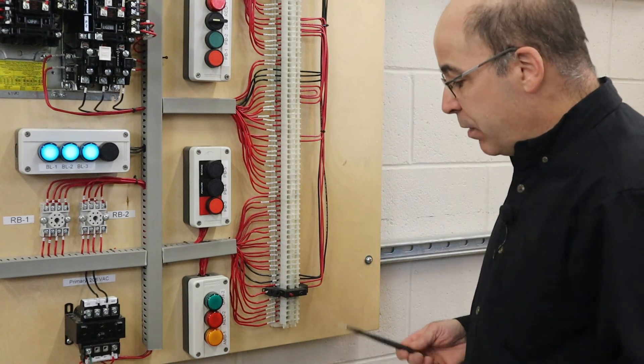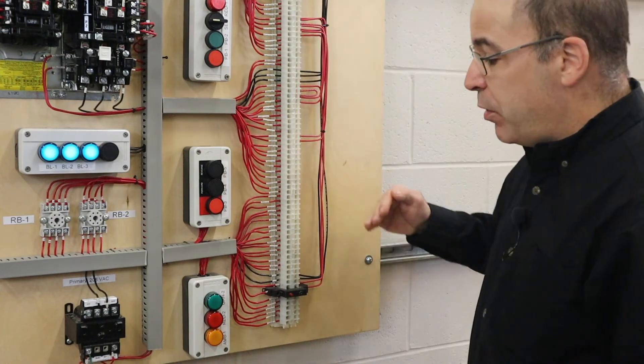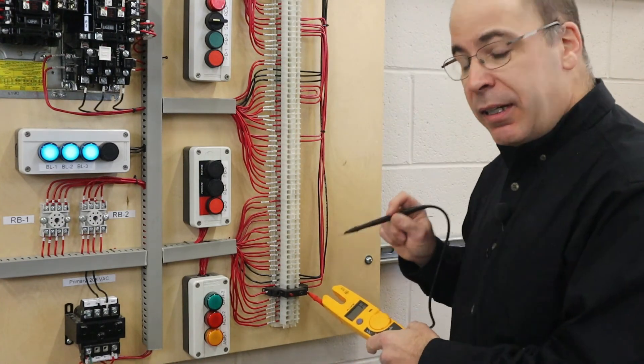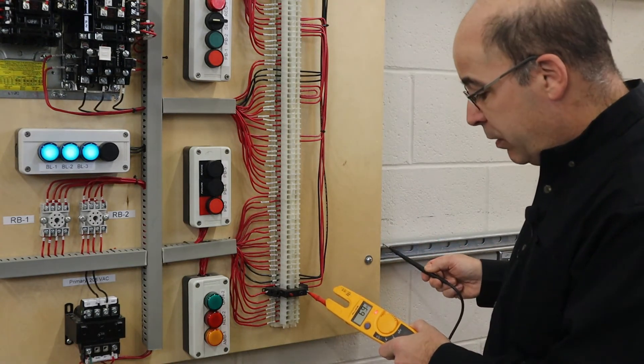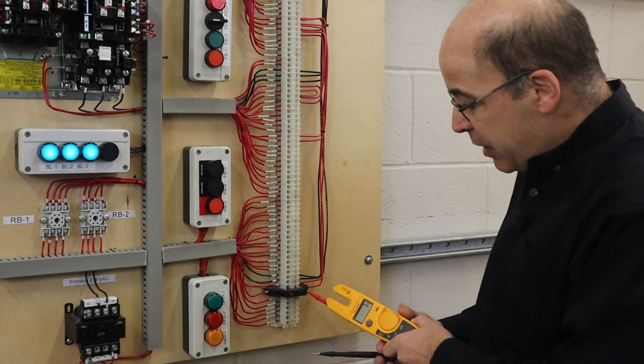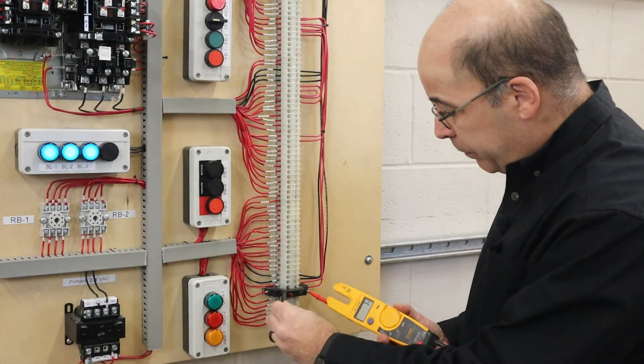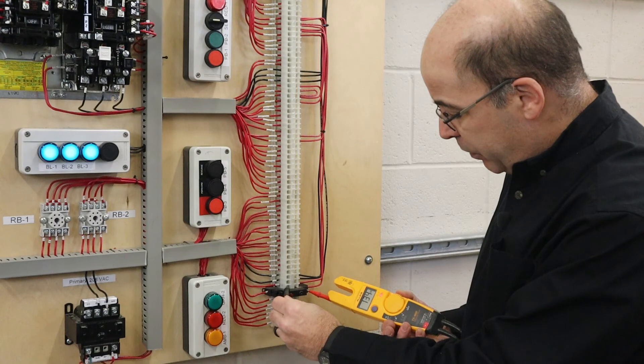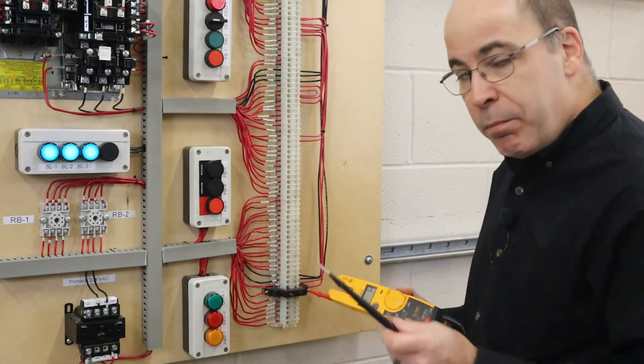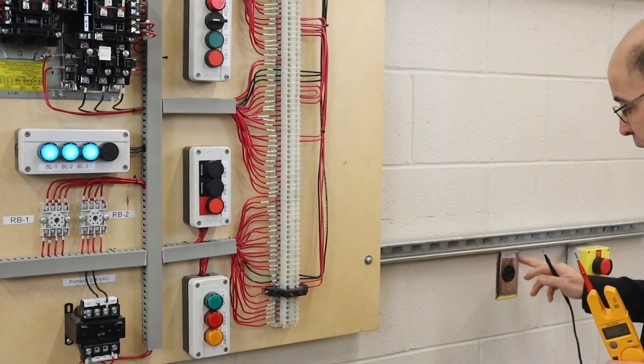Now we're going to take readings from the output of my circuit breaker, which is going throughout the circuit. And we're going to take it referencing this ground point. Well, we think it was a ground point. And what we see is 69 volts on the multimeter. This is incorrect, because if I take our reading to X2, I'm still getting 134 volts. This is not bonded.